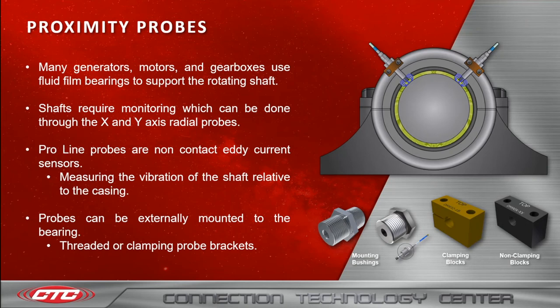The probes are mounted 90 degrees apart for the X and Y axis readings. Our ProLine probes are non-contact eddy current sensors which measure the vibration of the shaft relative to the casing. Our probes can be externally mounted to the bearing using threaded or clamping probe brackets, as shown in the bottom right.